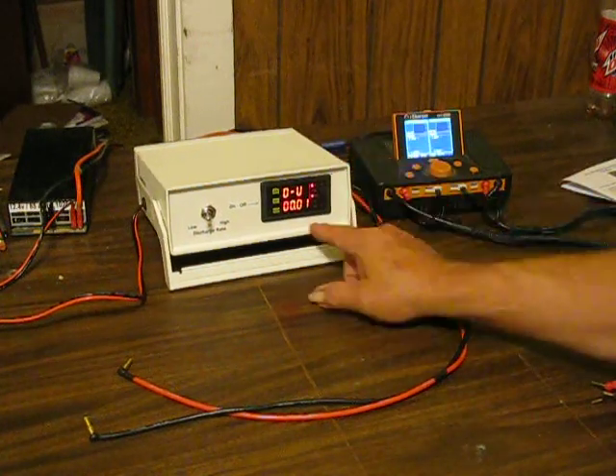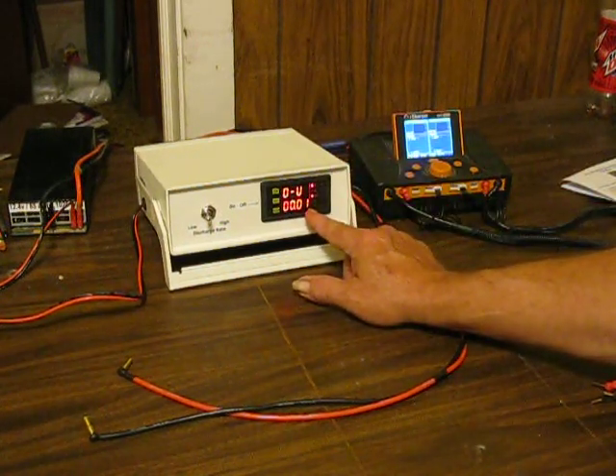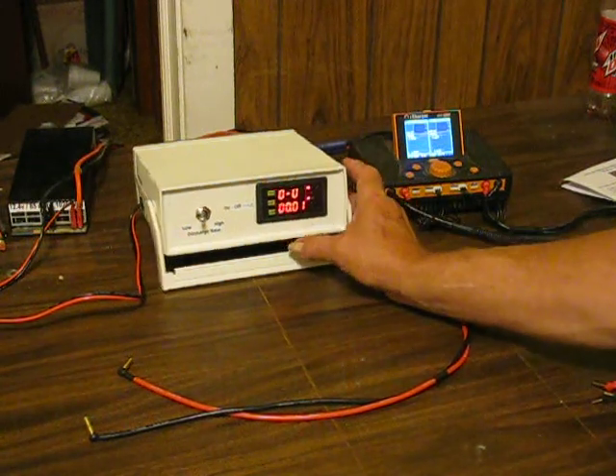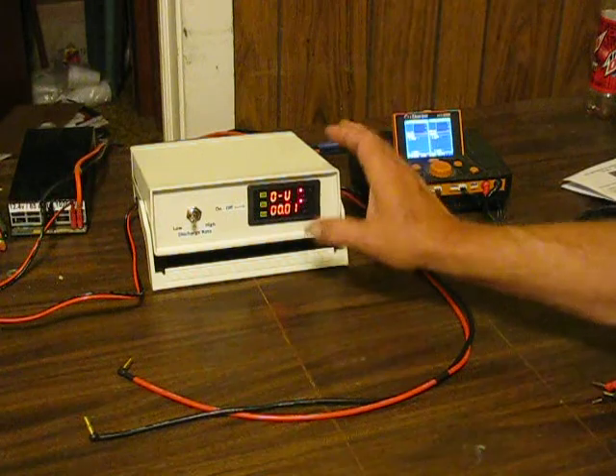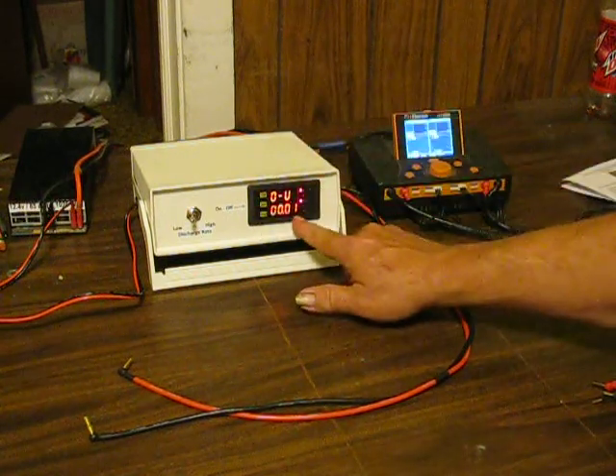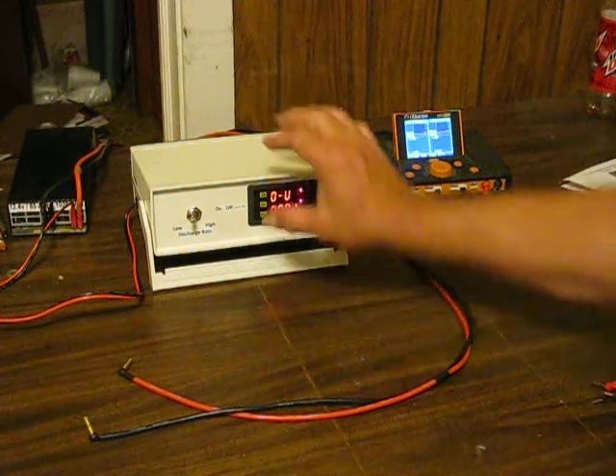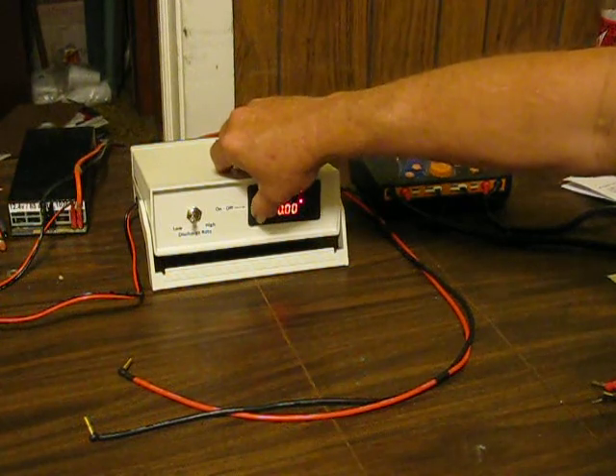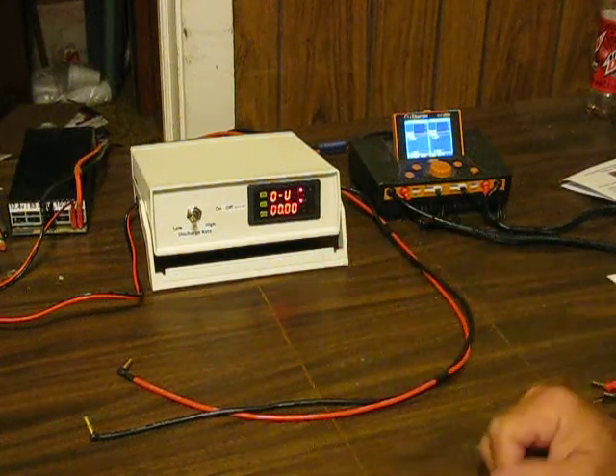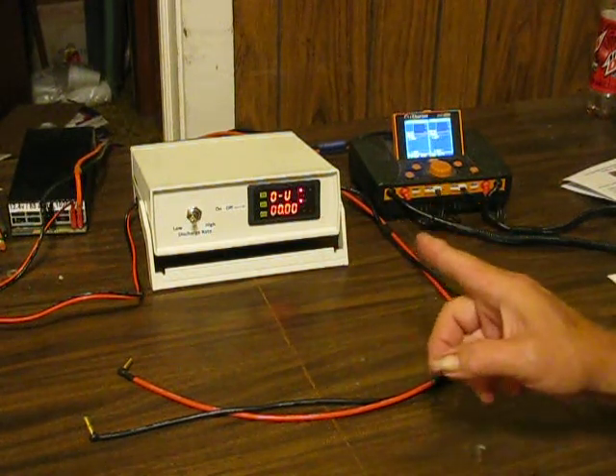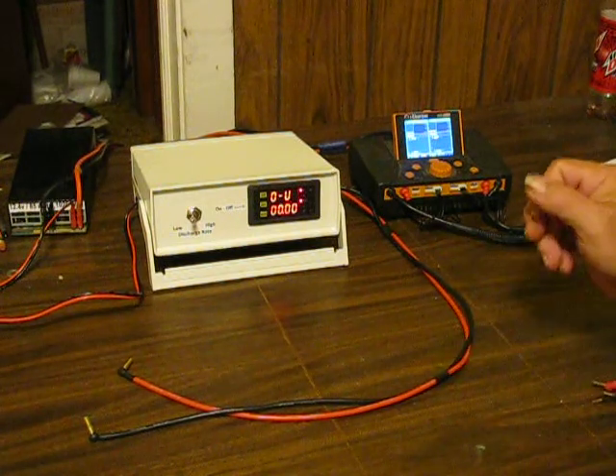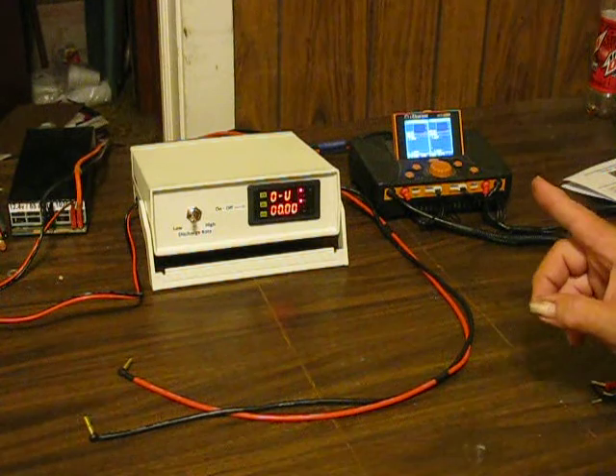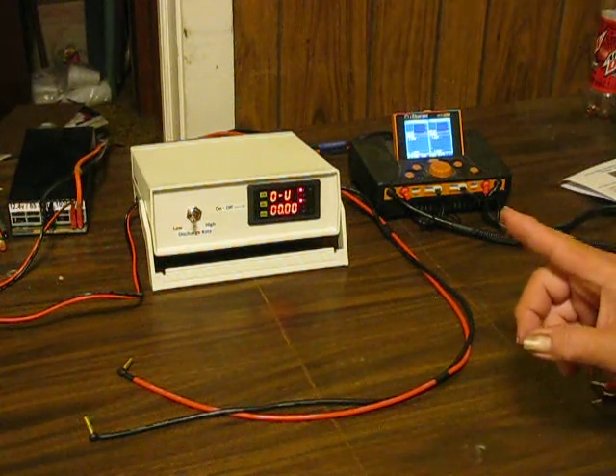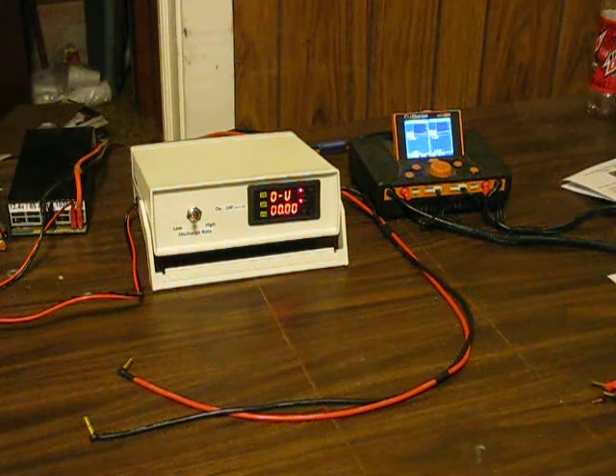Once it's at 0.01, we want to bring it on down to 0. We want to hit that lower button slow, or real quickly. Don't hold it down until that reading is at 0.00. You might have to go a couple clicks more to get it to stay at 0.00. That's the low calibration of the voltage that we just set. Now we'll go through and set a couple other things so we can get the high display correctly displayed.